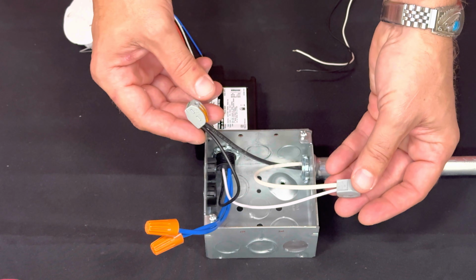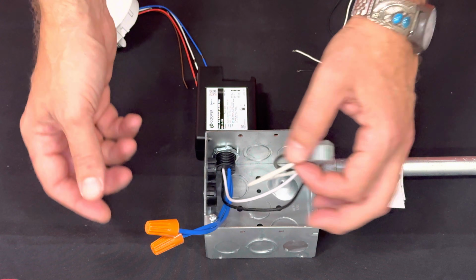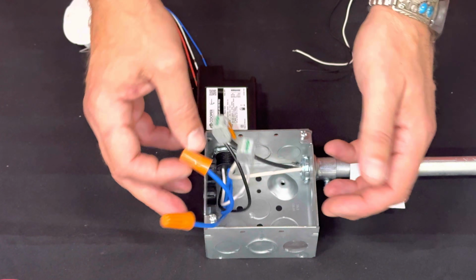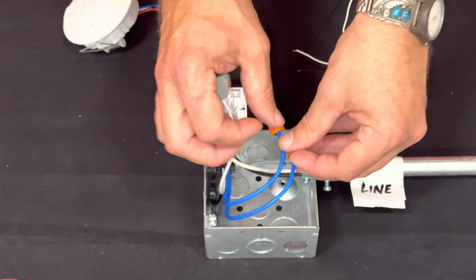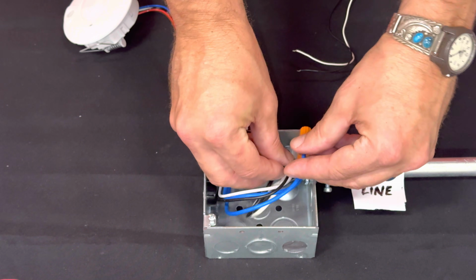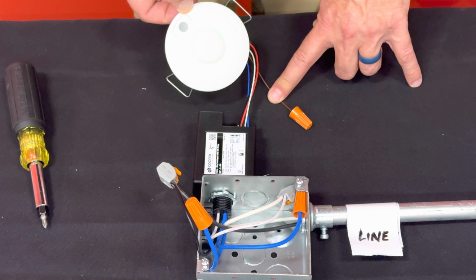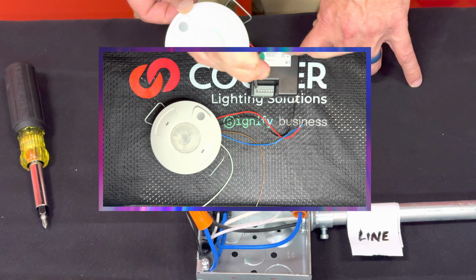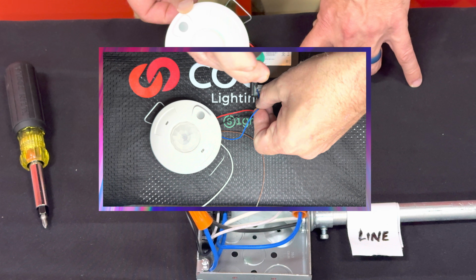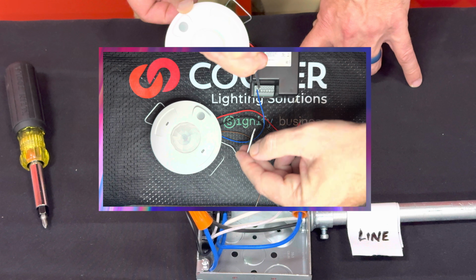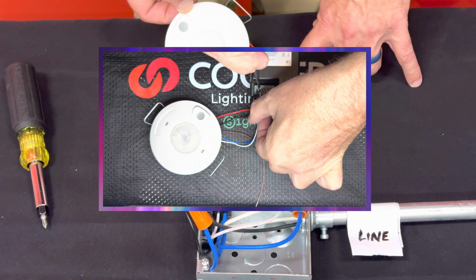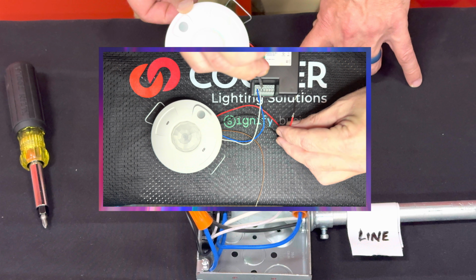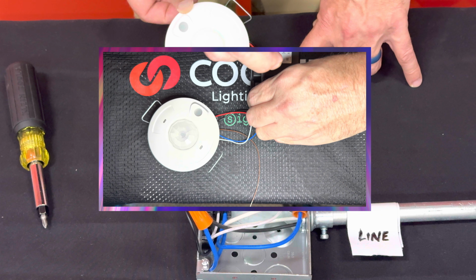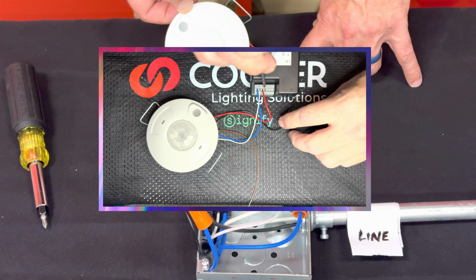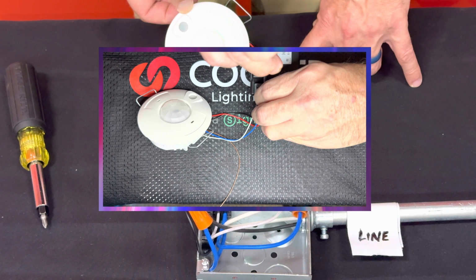If the RSP-V is not controlling a load directly and instead controlling a remote RSP-L, for example, the blue switched legs from the RSP-V can be capped off. RSP-V low voltage wiring. The blue wire from the sensor connects to RSP control. The white wire from the sensor connects to BAS control. The red wire from the sensor connects to 24 volts plus, and the black wire from the sensor connects to GND.